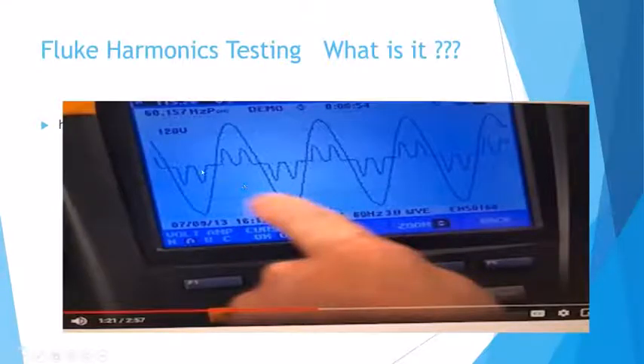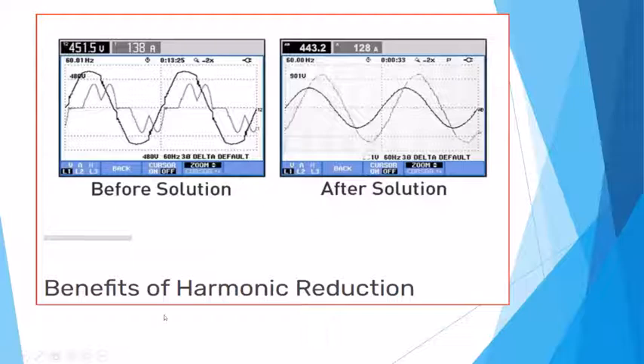But the meter allows us to see all those blips, all that information, so we can see what's going on. This happened to be before they put the harmonic filter on and after. It also has a deviation in total power. So this was the same load. This was the before solution, read at the 450 resultant volts here times 138 amps. And then the after was the average of 443 volts and 128 amps for the same load. So the load power, the total kilowatts used, is amps times volts and then also times power factor. But on the front of a drive, it ends up being in the 90s, so you don't have to worry too much about it.